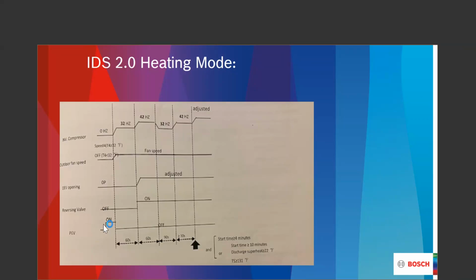For 4.5 years or so, we've always said that the IDS product does not want to have a programmable set thermostat in the heating mode. And you can see here that this is the reason why. What happens here when we go from an off position on the controller to a heating mode on the controller to a heat call out there on the IDS unit, we see here that we have this particular situation, no hertz.